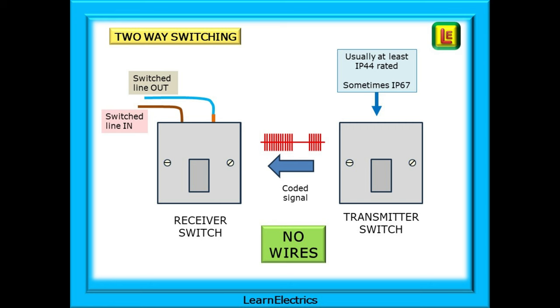For two-way and intermediate switching, no longer do we need to run strapper cables between switches. The first switch has the 230 volt switch wires fed into it and that is where the need for 230 volts stops. The second switch is completely independent and can be located anywhere as it has no 230 volts and needs no wires. The transmitter switches are usually rated at IP44 or better, even IP67, so can be installed in bathroom locations and are available with no screw holes on the front so they can be glued onto tiled wall surfaces without needing to drill through tiles.